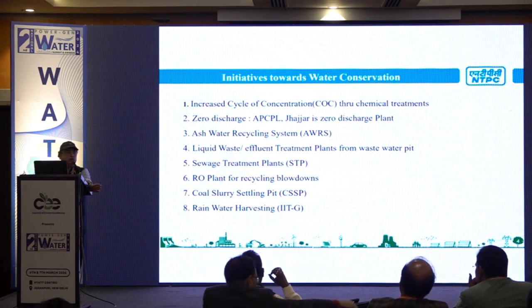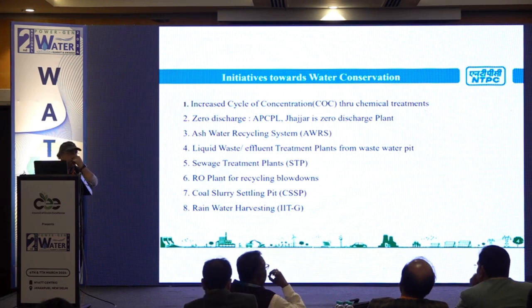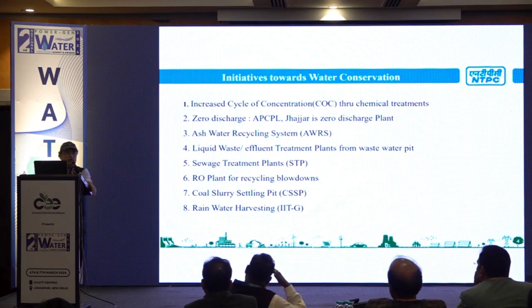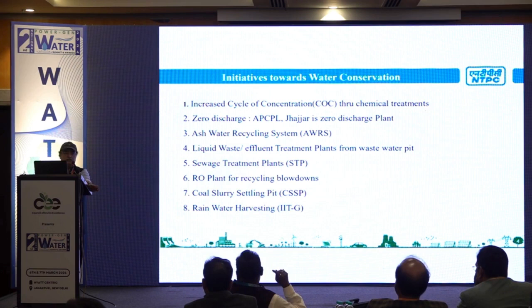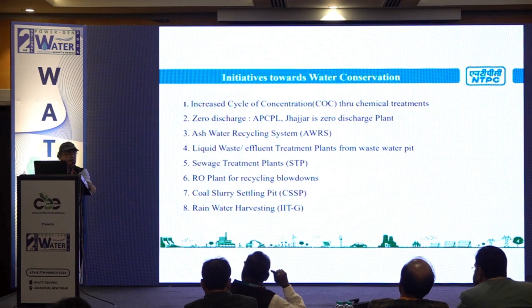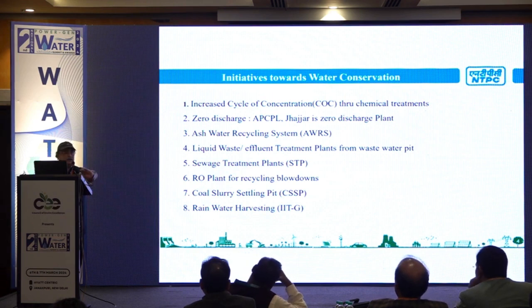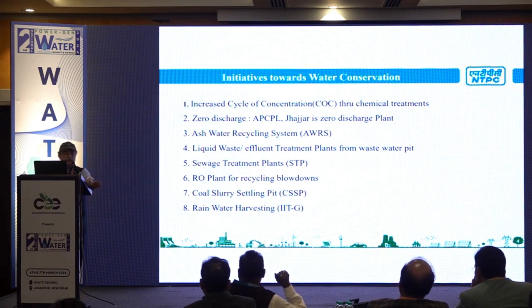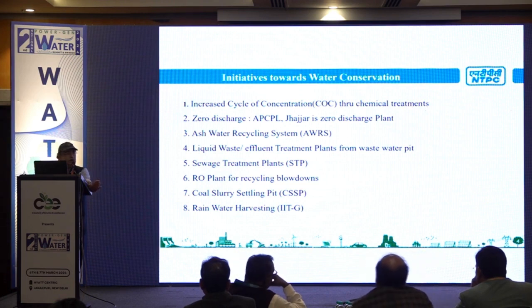We have an RO plant of 225 into 2 meter cube per hour capacity, and with that we are able to manage blowdown of the magnitude of 450 meter cube per hour. It is a 3-stage RO plant, meaning almost 85% recovery, and 15% is the reject effluent, which we use for our coal handling plant for dust suppression. There is also a coal slurry settling pit which utilizes hot drains coming from the coal handling plant, and that is again recycled to the coal handling plant for dust suppression. Though that quantity is very small, we are recycling that too.